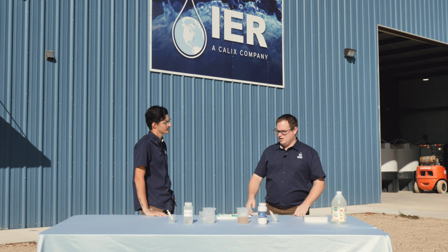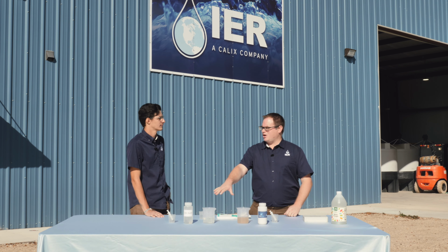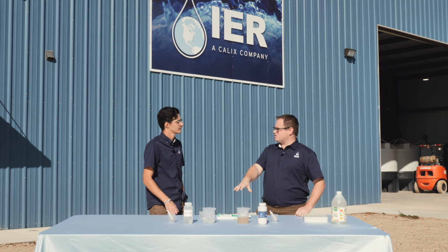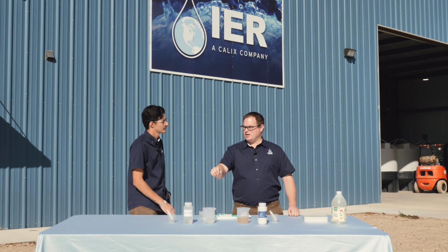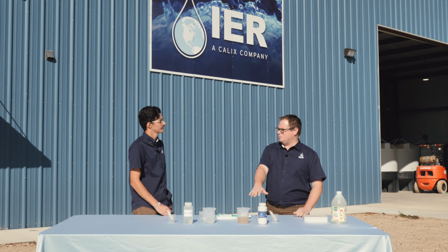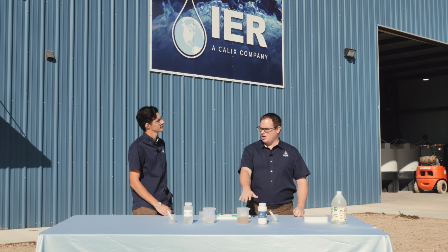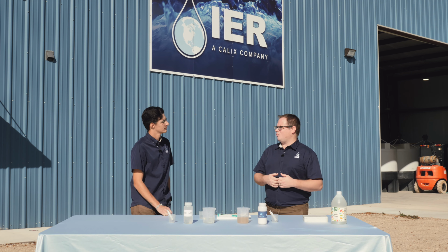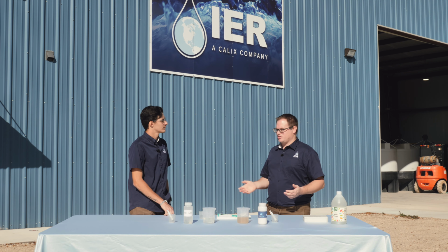The other thing is because caustic soda wants to get rid of that hydroxide, if you go one drop over what's needed, now you have a very hazardous wastewater that is now too high in pH. Magnesium hydroxide will not want to release that hydroxide. So you rarely will see a water dose with magnesium hydroxide get over a pH of 8, 9. So you have a safer one if it accidentally gets out into the water streams or anywhere else. You have less worry about the magnesium hydroxide having a detrimental effect on fish and the wildlife.